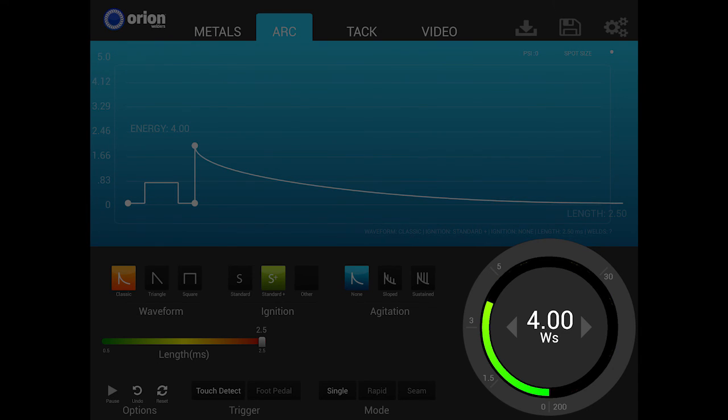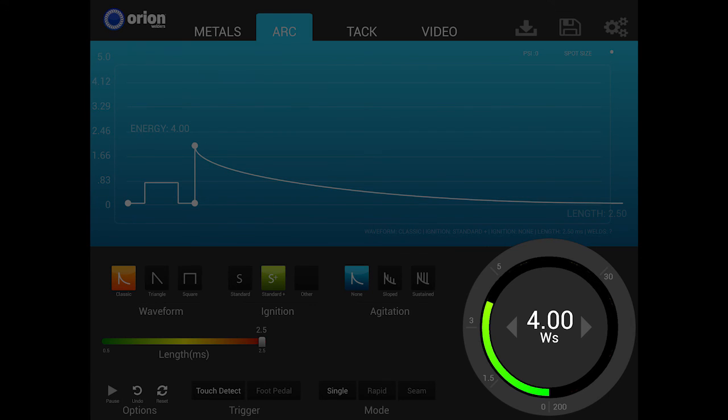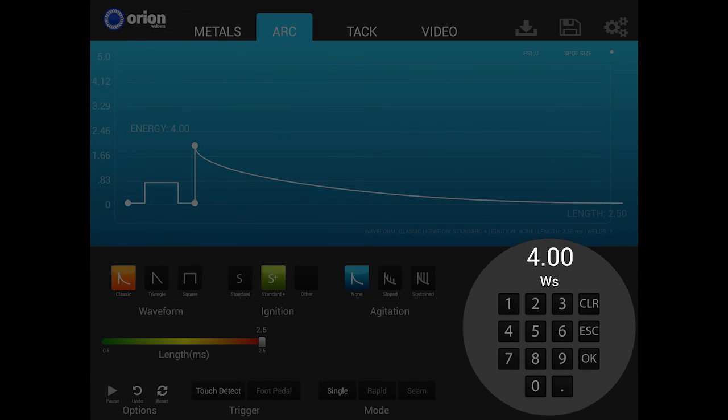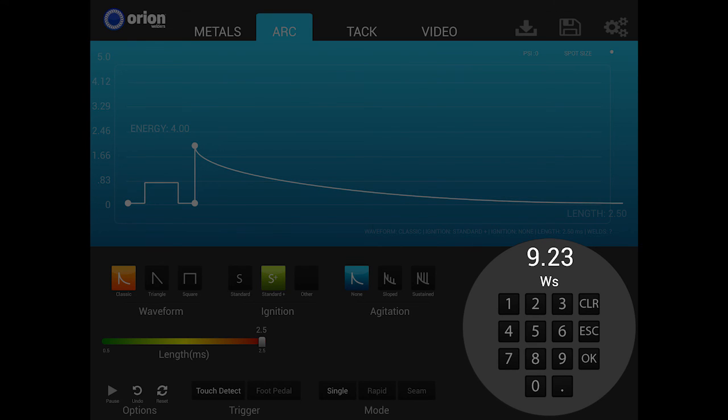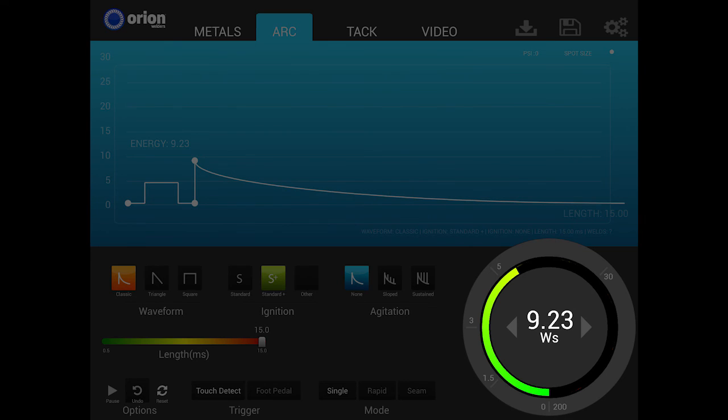Additionally, users can input the weld energy settings via a number pad. To access the number pad, tap on the weld energy number inside the dial. This allows users to directly enter the exact desired weld energy values. Once the numeric value is entered, tap OK to set the value and exit the number pad.